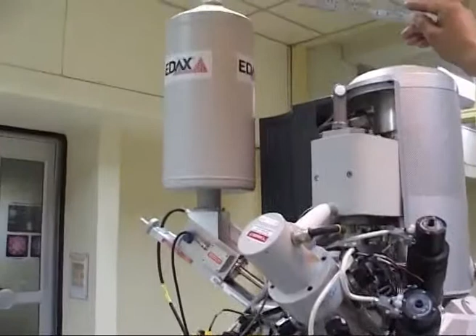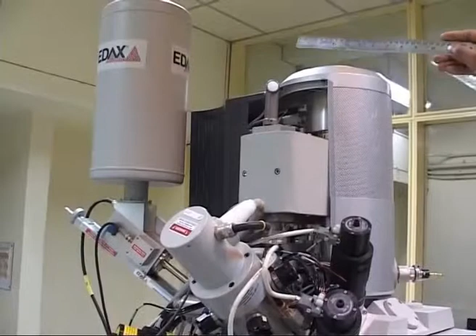So this is the electron beam as explained in the schematic, and this one is the ion beam, and these are the three precursor gases we have, 1, 2, 3. These correspond to platinum, tungsten and carbon. This one is EDAX, energy dispersive X-ray spectroscopy, used for elemental composition mapping of the substrate. Whenever an electron hits, various phenomena take place like secondary electron ejection and X-ray emission, so there is one more detector for X-ray detection, and this is helpful for elemental mapping.